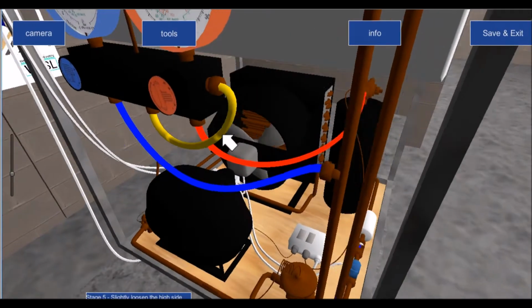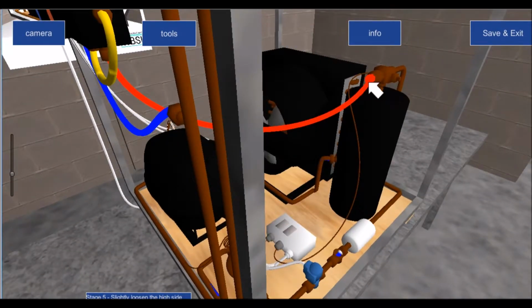And that's what allows us to carry out our purge, which is literally just allowing enough vapor to escape out of the red line. It's a judgment call. We have to remember that it's going to be a very small amount of air in the system. So what we're trying to do is leave it purging for long enough so that we know there's no longer air coming and there's only refrigerant coming out.